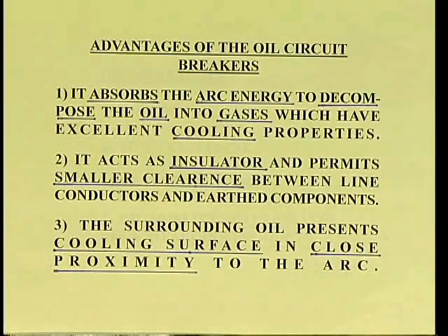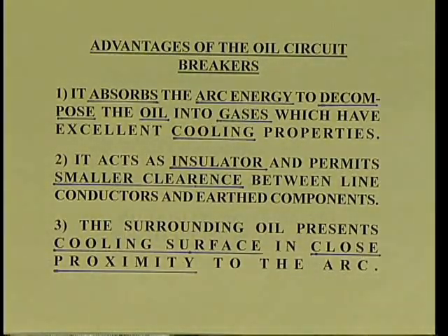Third advantage is the surrounding oil presents a cooling surface in close proximity to the arc. It also aids deionization, that is, aids the dielectric strength of the medium. So these are the advantages of oil circuit breakers.